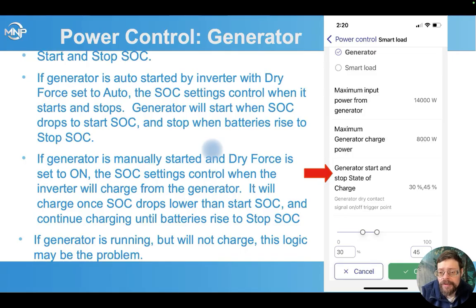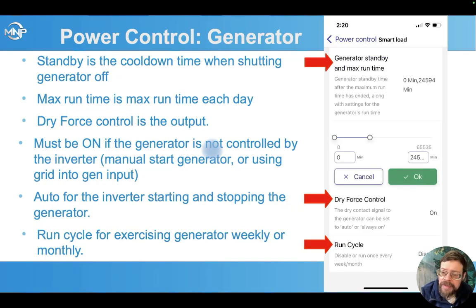Like we discussed, when you're looking at your start and stop state of charge, if you're auto starting, this is when you want it to start and when you want it to turn back off. If you're manually starting it, you want to set these really high so that it'll always be below them when you manually start the generator, and it'll accept that generator input. And then you want to set your dry force control to on if you're using a manually started generator, and auto for an auto start. Set your maximum standby and max runtime. Standby is your cooldown time, and max runtime is per day, remember.